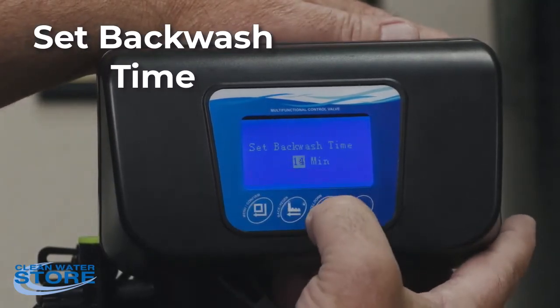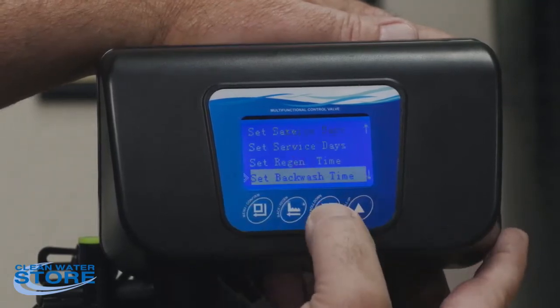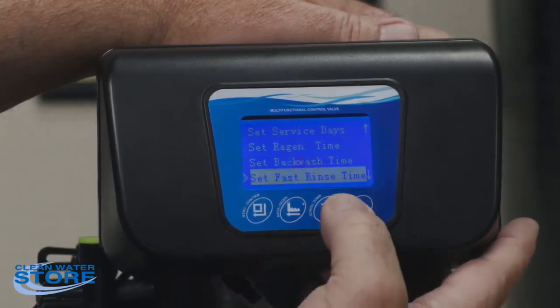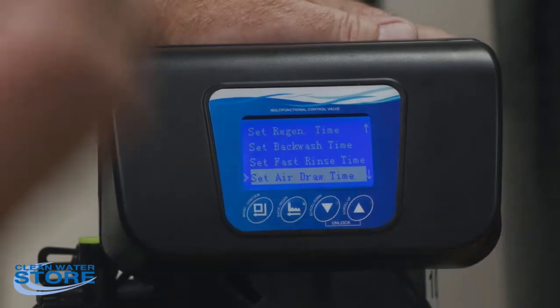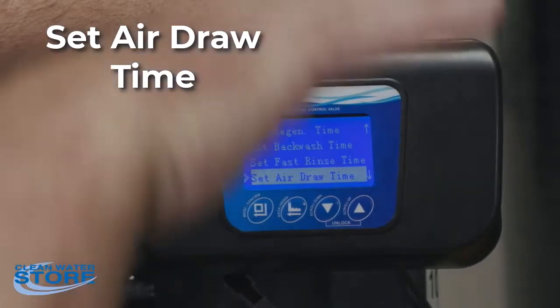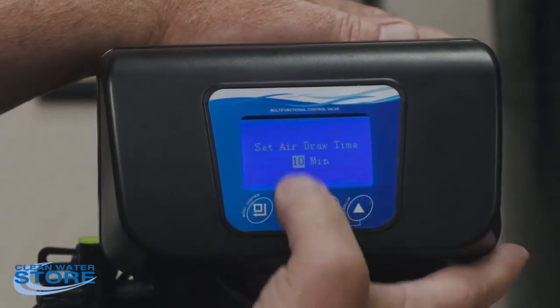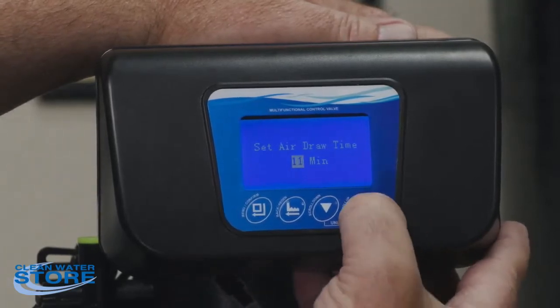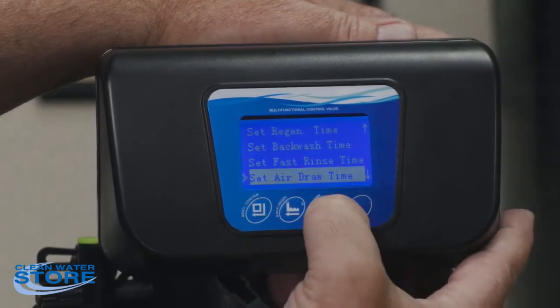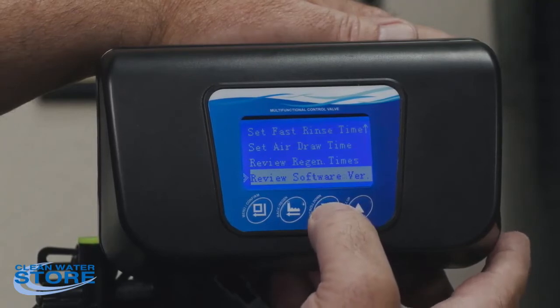Backwash time is 10 minutes standard, so we'll take that to 10. Fast rinse time is 8 minutes — again, these are all set here as standard. Air draw time is the time you're actually running a little water through the injector and recharging the air — that should be set at 10 minutes as well, which it is here. You can scroll that up and down if you want to change it.